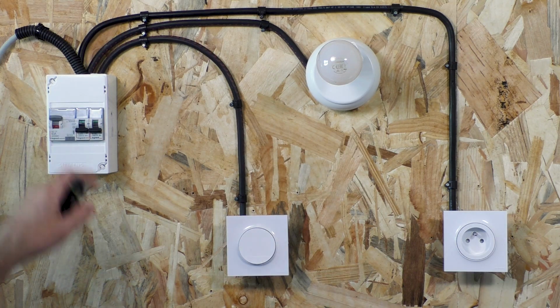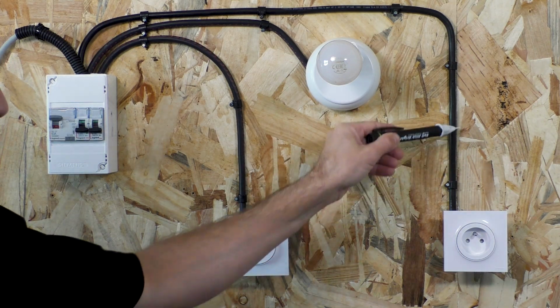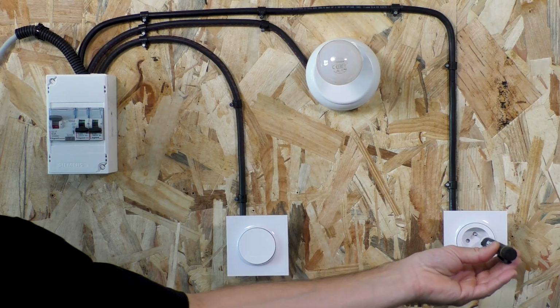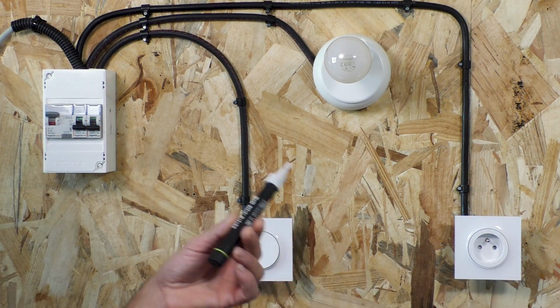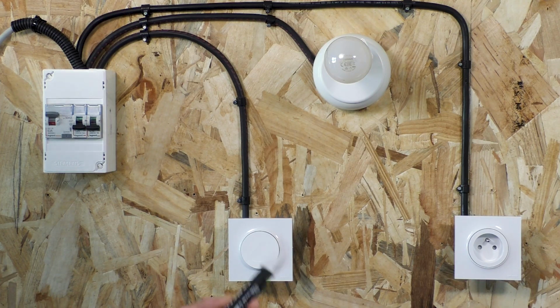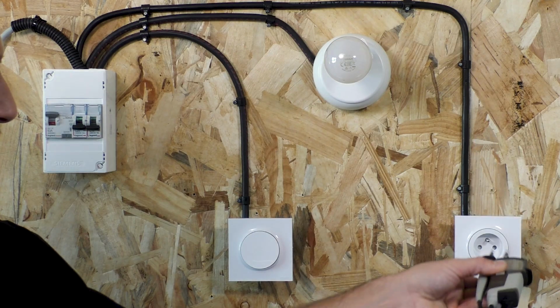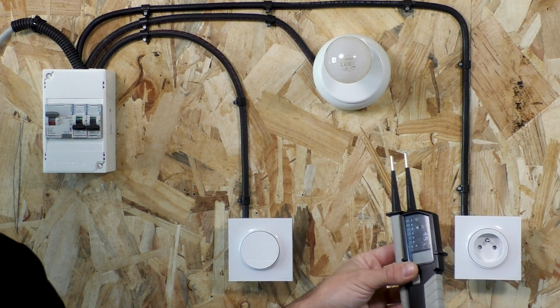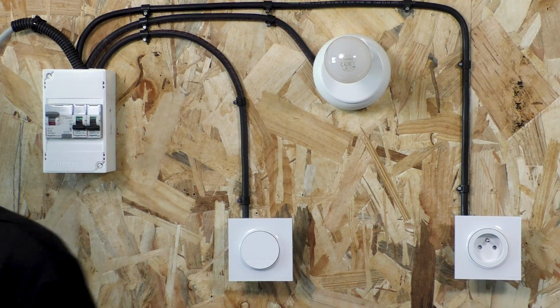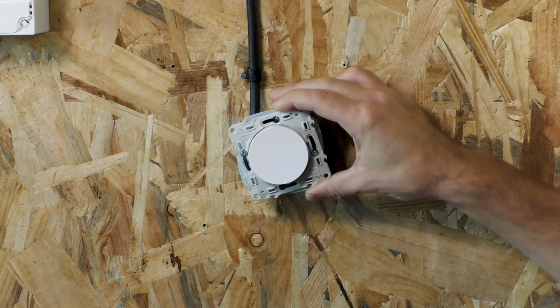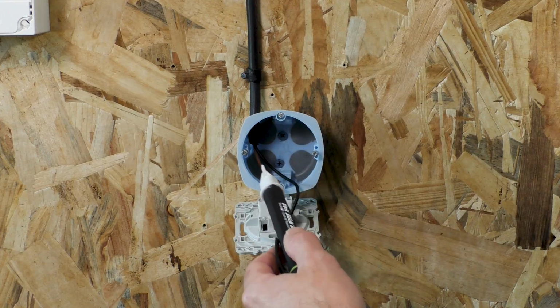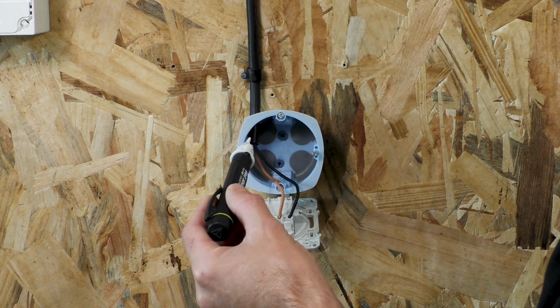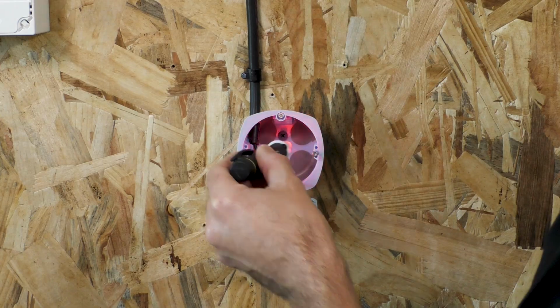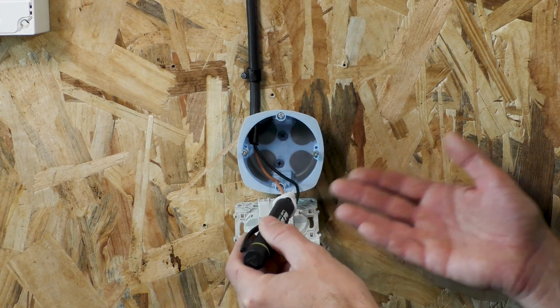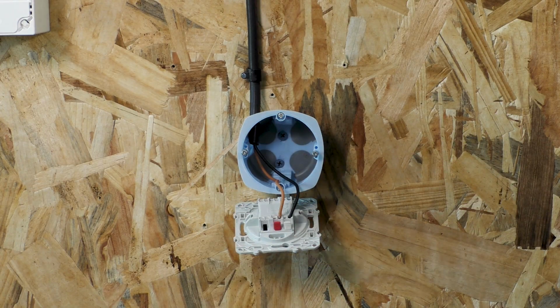Now if I turn the breaker off and test again, nothing. No light, no beep. Now this tool is especially useful or even necessary in situations when there is no neutral wire, like at the light switch. A multimeter or a tester with probes measures voltage between live and neutral. So if the neutral isn't present, it won't show you anything. But a contactless tester can still tell you if the wire is live, which makes it perfect for checking switches or single live connections.